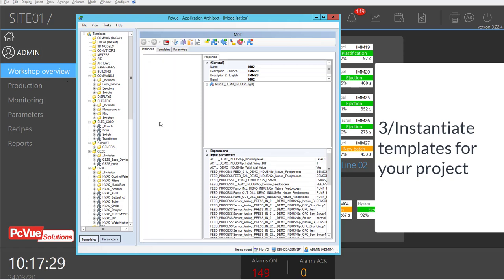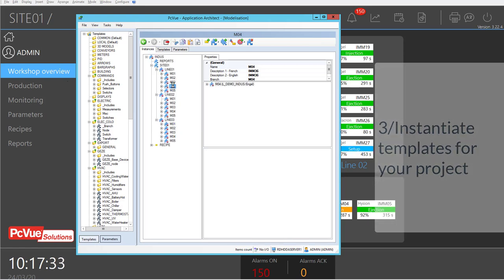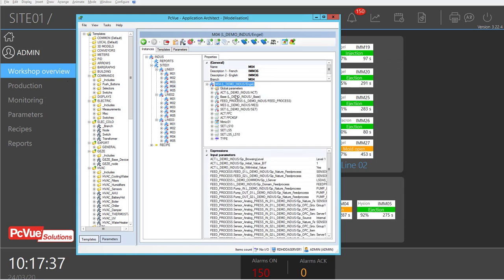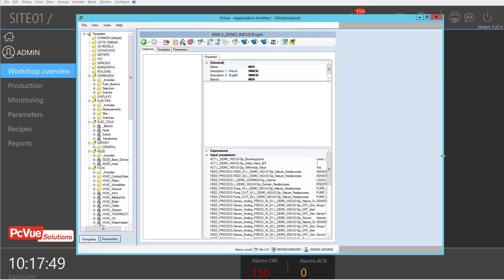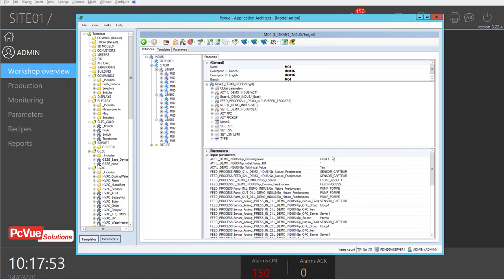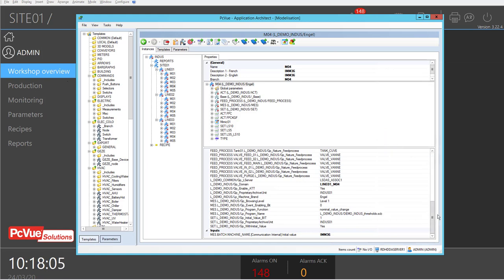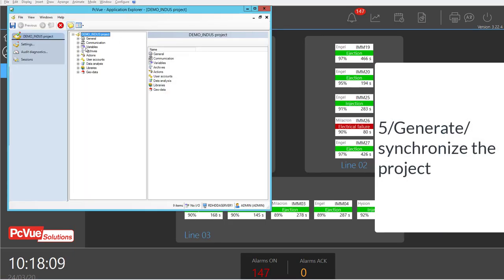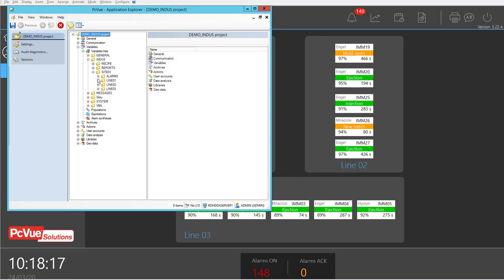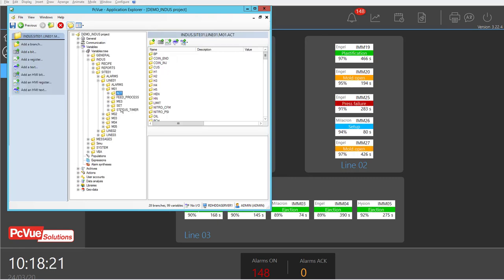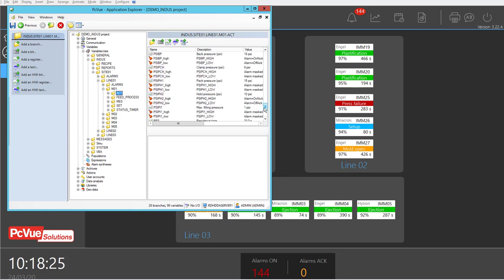You then create instances to match the physical process exactly. Here we have three lines, each line has five machines, and for each machine we instantiate a machine model containing all sub-models and sub-templates with all values. Each machine instance has a set of parameters you can define at instantiation time. This is very efficient for the developer and saves significant time during project design and development. In the Application Explorer, all variables are created according to the defined and instantiated templates.